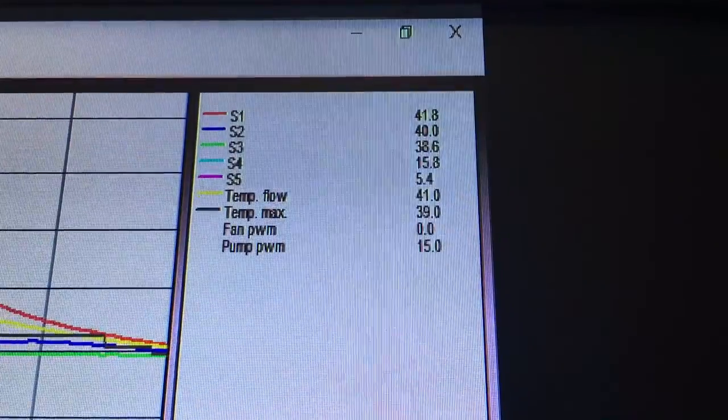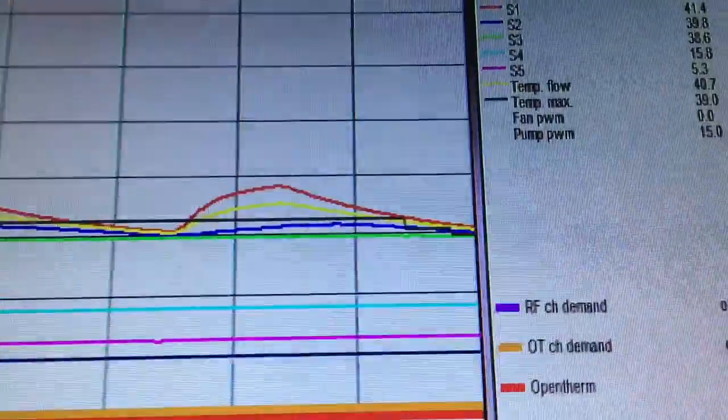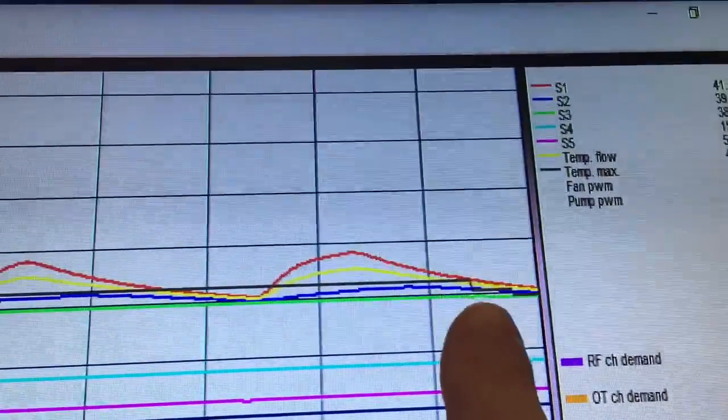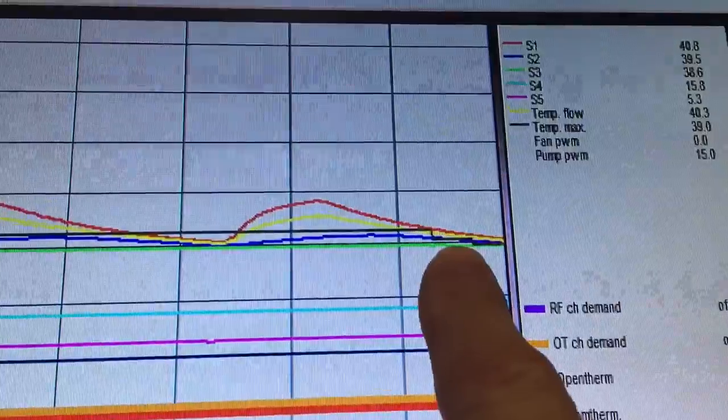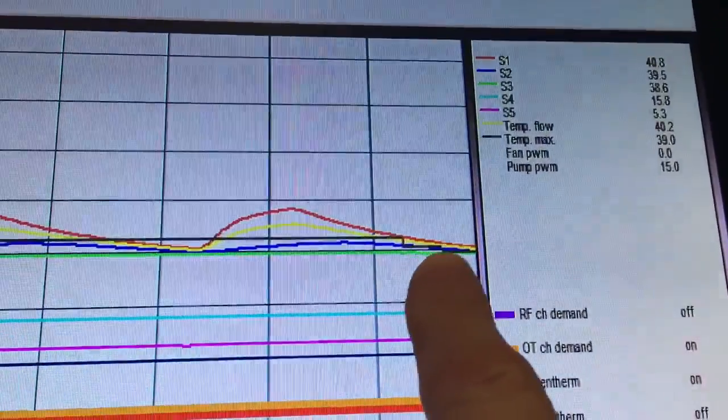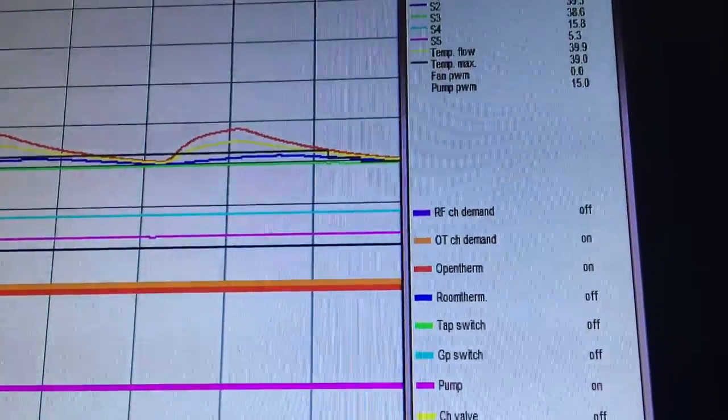So as you can see, the parallel shift works, and you can see it on the graph here. So if you look at the black here, you can see that it was at 45, then it went down to 41, and now it's gone down to 39 degrees. So you can see the parallel shift in operation there.